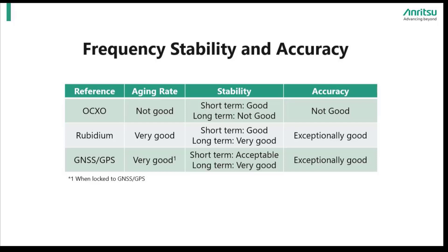Next we have Rubidium and GNSS GPS references. They both display very good aging rates. With negligible differences in stability, users can expect exceptionally good accuracy and now have choices for an accurate reference depending on their specific measurement applications.